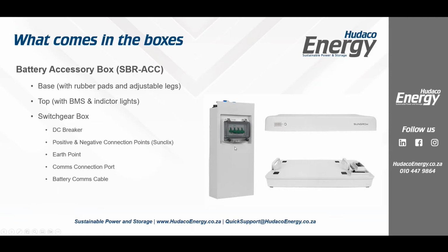And then finally, your switchgear box. Now in here, you've got your DC breaker. You've also got your positive and negative connection points. Now, those come with Sunclix connectors. The reason they come with the Sunclix connectors is because your cable is the same as your PV cable, so we don't want to mix it up. You don't want to get it wrong and have your batteries plugged into your MPPTs, or vice versa. These are also supplied in the box, not just the 2 for here, but also the 2 that go on the other side of your cables as well. In fact, you get 4 of them, so for both sides of the cables, so that you just clip them in when you're ready.